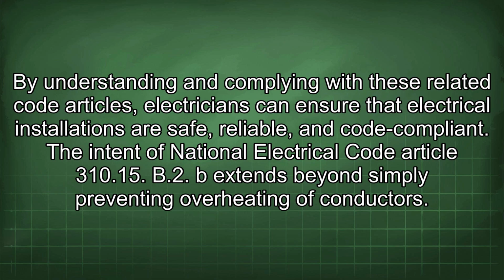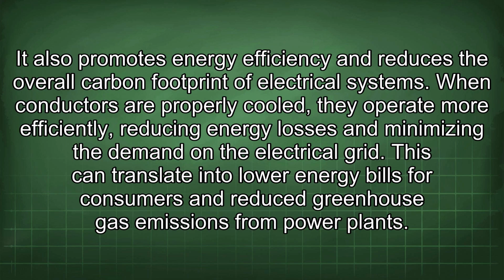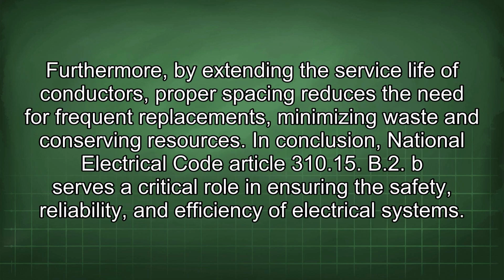By understanding and complying with these related code articles, electricians can ensure that electrical installations are safe, reliable, and code compliant. The intent of National Electrical Code Article 310.15.B.2.b extends beyond simply preventing overheating of conductors. It also promotes energy efficiency and reduces the overall carbon footprint of electrical systems. When conductors are properly cooled, they operate more efficiently, reducing energy losses and minimizing the demand on the electrical grid. This can translate into lower energy bills for consumers and reduced greenhouse gas emissions from power plants.